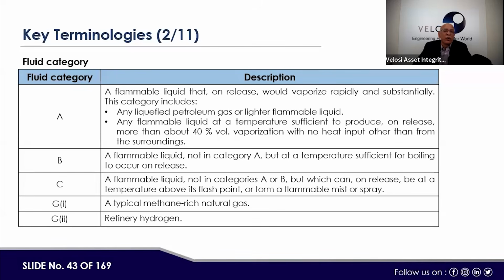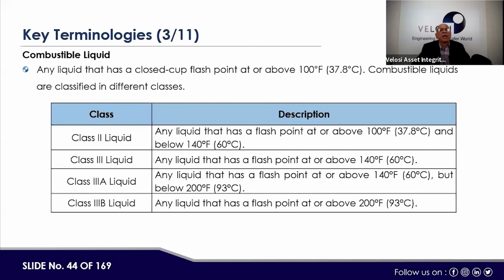Then fluid category B, a flammable liquid not in category A but at a temperature sufficient for boiling to occur on release. Then category C, a flammable liquid not in category A or B but which, on release, can be at a temperature above its flash point. Then typical methane-rich natural gas is G1, and refinery hydrogen is G2. Similarly, the combustible fluids are also classified as class 2 liquid, class 3 liquid, class 3A liquid, class 3B liquid. This is the same temperature limit as we explained earlier.